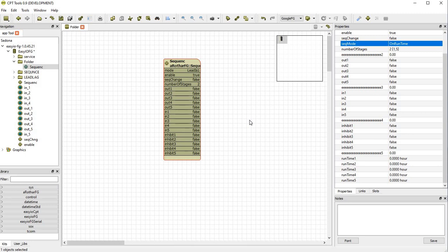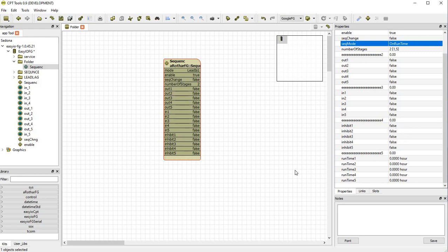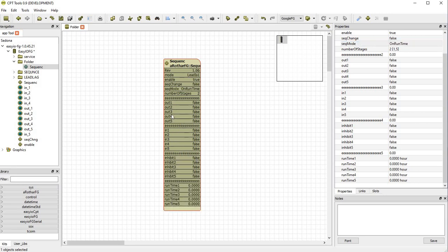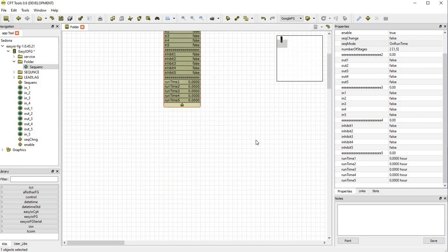We had various meetings about whether to utilize a status for the runtime, but ultimately a fault input will stop that runtime anyway. If you didn't want the internal runtime, you can externally link a runtime to these points here available through this drop-down. You can just link to this and it will use an input of runtime read either from the equipment itself or based on how you want to determine runtime.